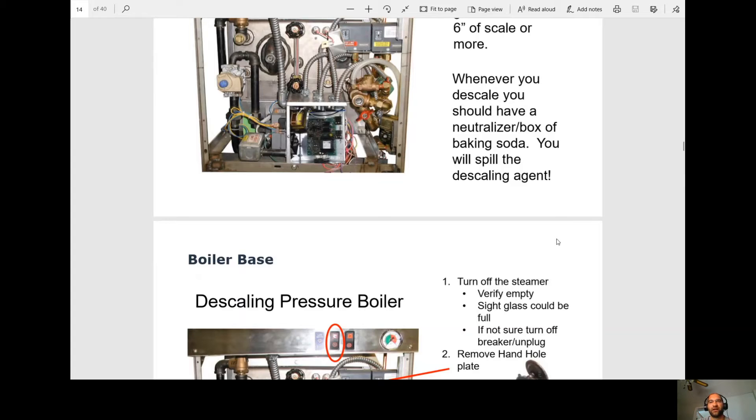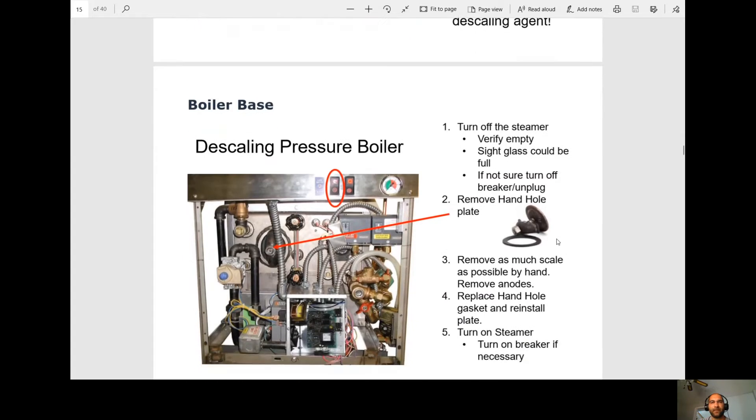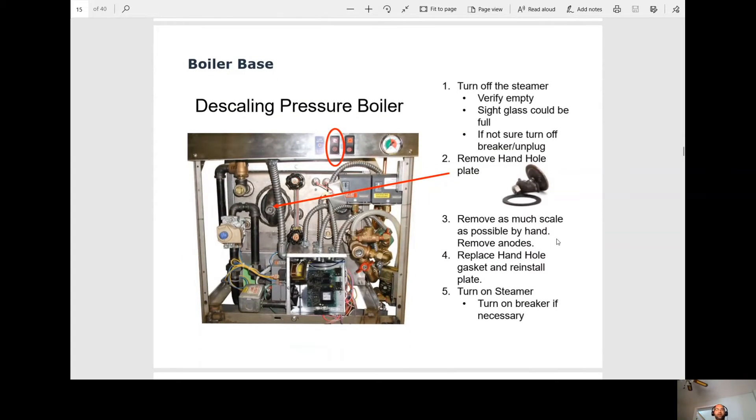Whenever you descale, you should have a neutralizer or a box of baking soda just in case you spill the descaling agent. So for a boiler base, for descaling, these are the steps. First thing, turn off the steamer. Verify it's empty. This sight glass here, it could be full because when we turn the switch off, we go down into our blowdown. Usually, it's up to three minutes, that blowdown. If it's slow to drain, this sight glass is actually going to fill up because when we go in our blowdown, we're introducing water in there so we can move any scale, push any scale off every time we turn the unit off.